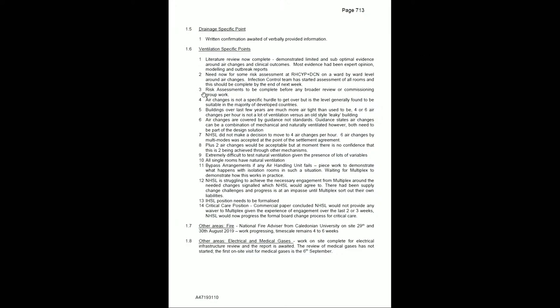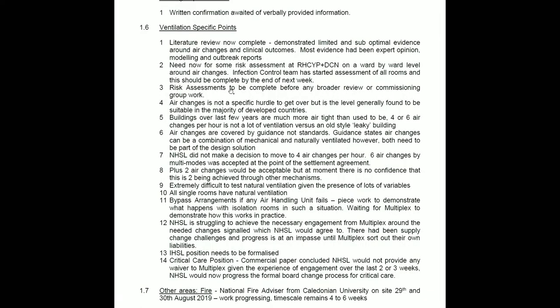What it says here, under the heading of ventilation-specific points, says literature review now complete, demonstrated limited and suboptimal evidence around air changes and clinical outcomes. Most evidence had been expert opinion, modelling and outbreak reports. Reading on at paragraph 4, air changes is not a specific hurdle to get over, but is the level generally found to be suitable in the majority of developed countries. And 5, buildings over the last few years are much more airtight than they used to be. 4 or 6 air changes per hour is not a lot of ventilation versus an old-style leaky building. Air changes are covered by guidance, not standards.